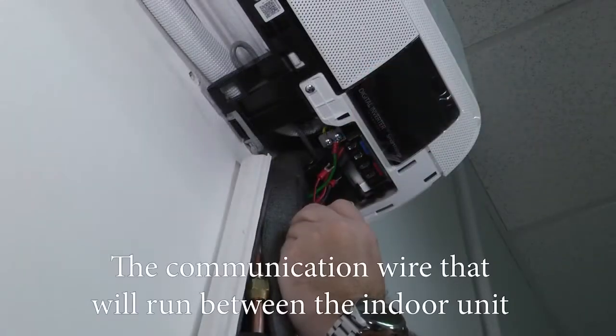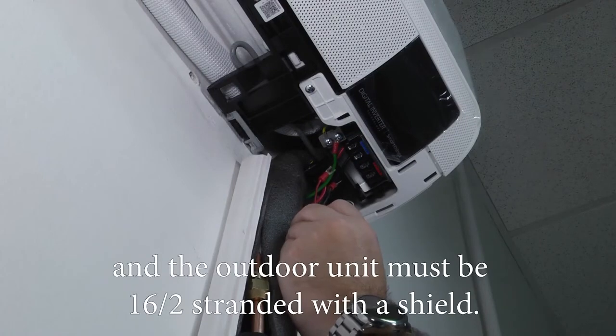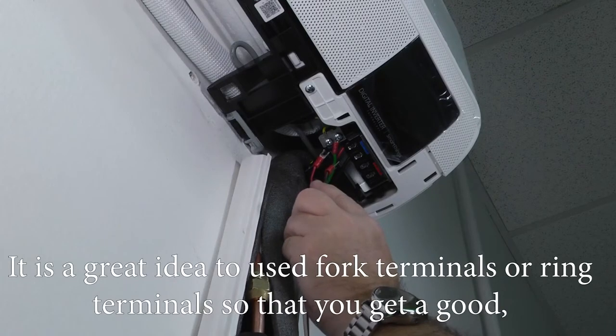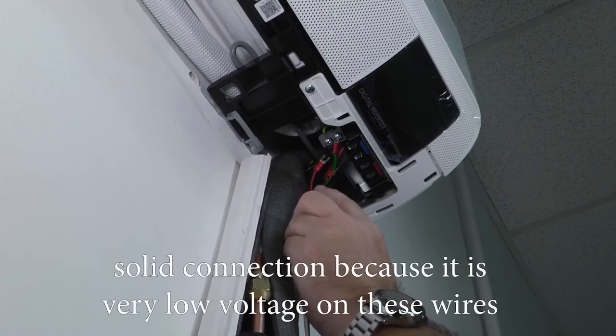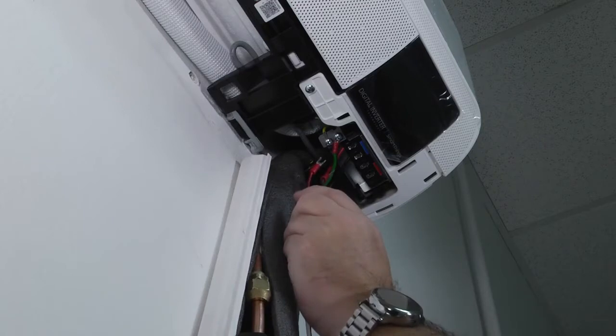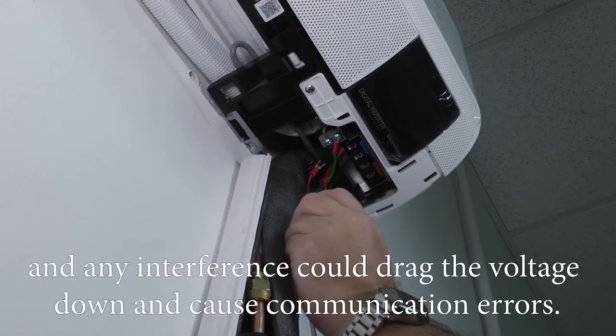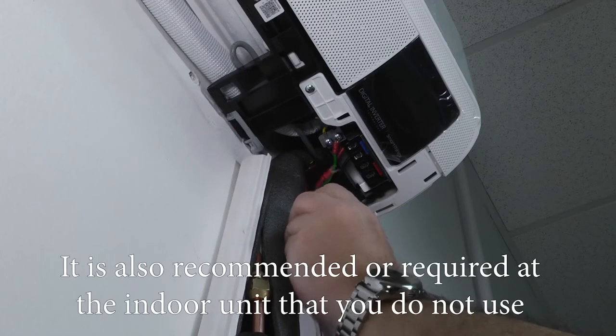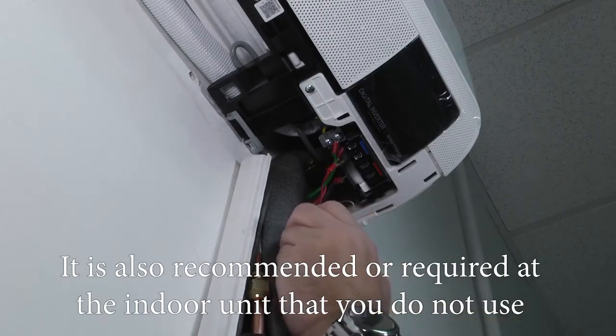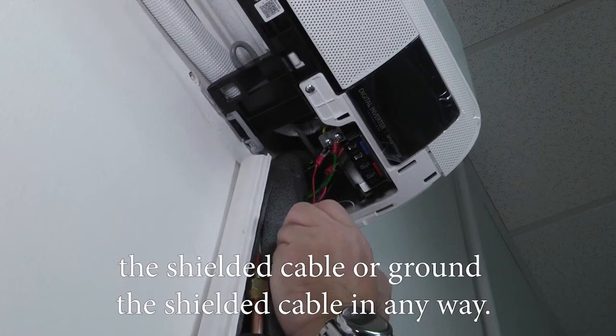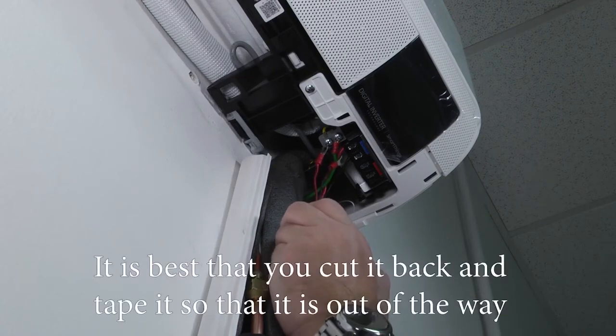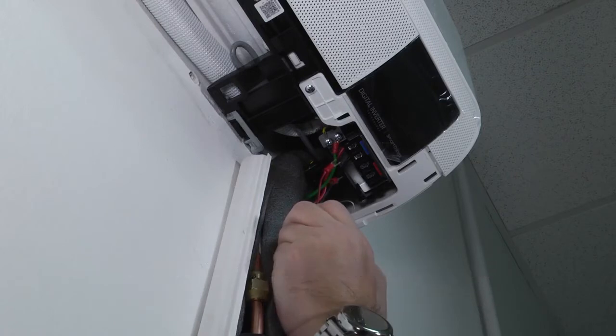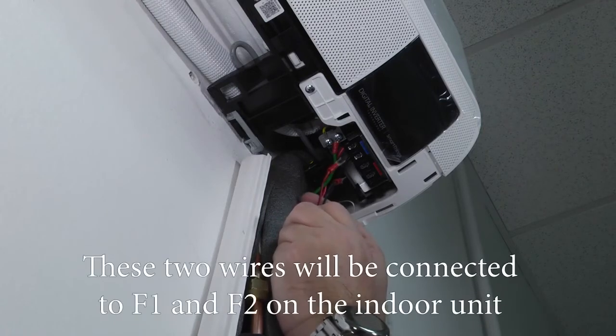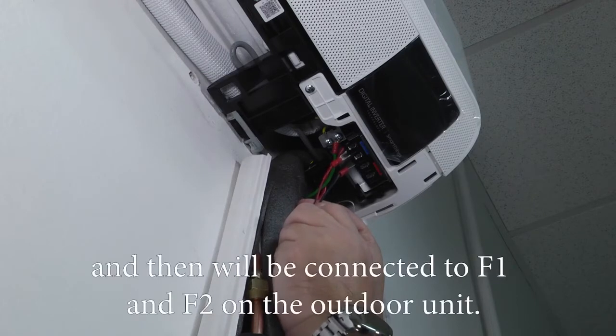The communication wire that'll run between the indoor unit and the outdoor unit must be 16-2 stranded with a shield. It's a great idea to use fork terminals or ring terminals so that you get a good, solid connection, because it's very low voltage on these wires, and any interference could drag the voltage down and cause communication errors. It's also recommended or required at the indoor unit that you do not use the shielded cable or ground the shielded cable in any way. It's best that you cut it back and tape it so it's out of the way to prevent any communication errors. Now these 2 wires will be connected to F1 and F2 on the indoor unit, and they'll be connected to F1 and F2 on the outdoor unit.